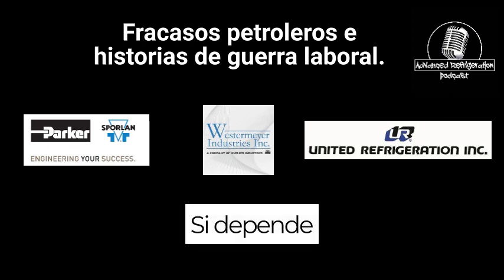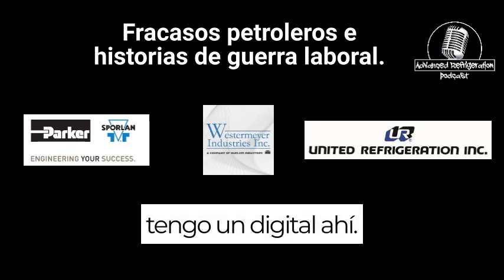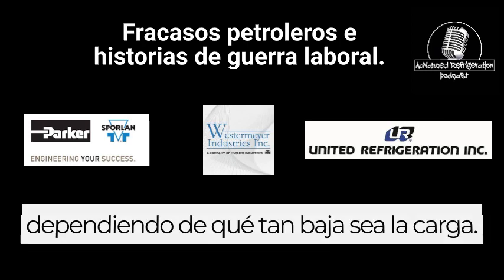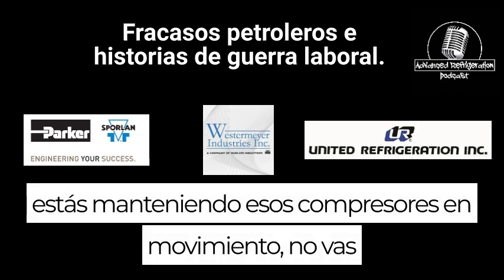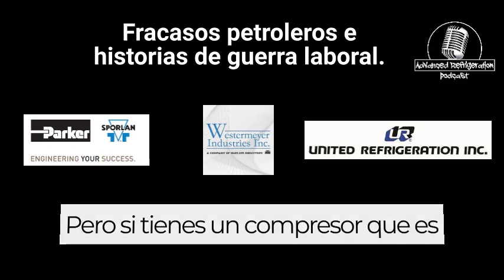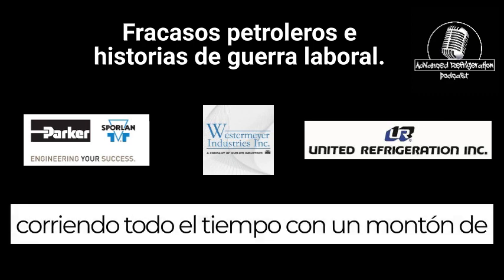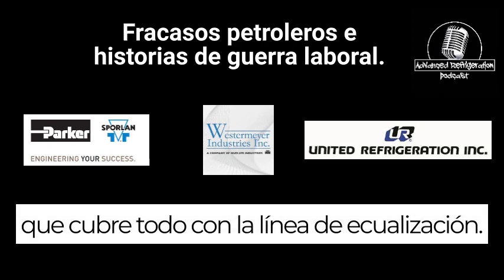It just depends. Like Copeland, if it's got a digital on there, you probably need to have it on there, depending on how low the load is. If you have a high load rack and you're enabling unloaders on the compressors and keeping those compressors moving, you're not going to have an issue in most circumstances. But if you have a compressor that is running all the time with a bunch of unloaders, you're probably going to need the equalization. I think that covers everything with the equalization line.